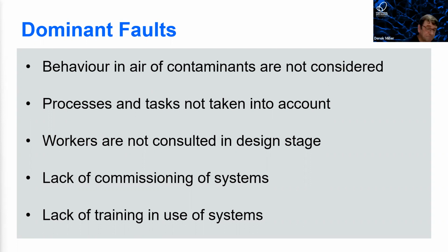The other big issue we tend to come across is lack of training in the systems. There's a system installed in a woodworking area. When we tested it, it had never been commissioned, but we went through the testing process and showed that it wasn't entraining the contaminants, it was struggling to capture.